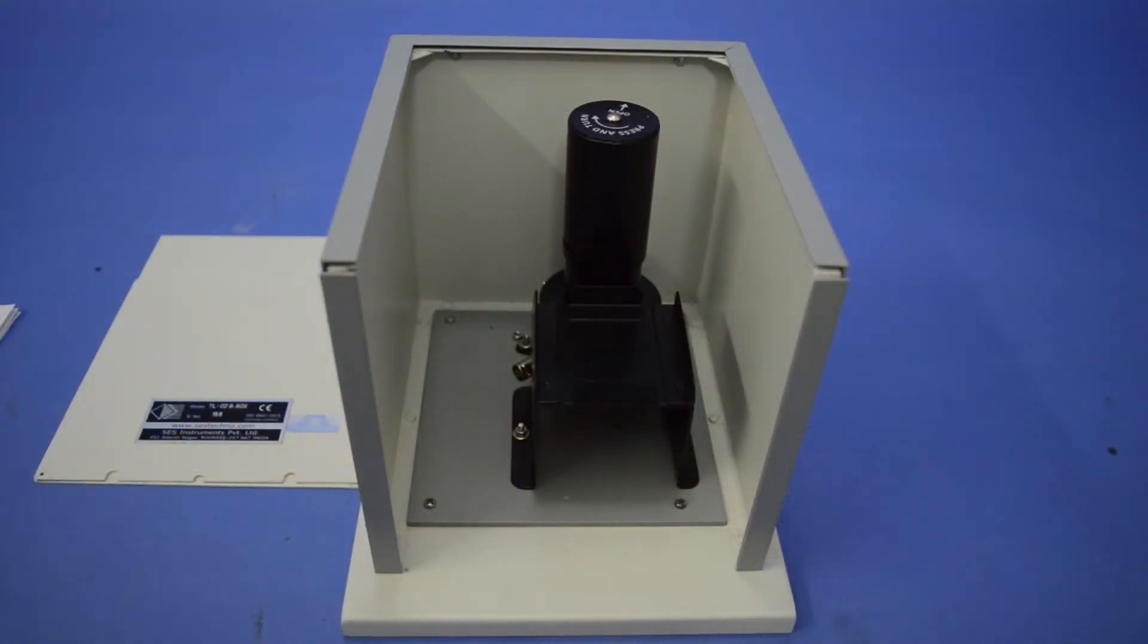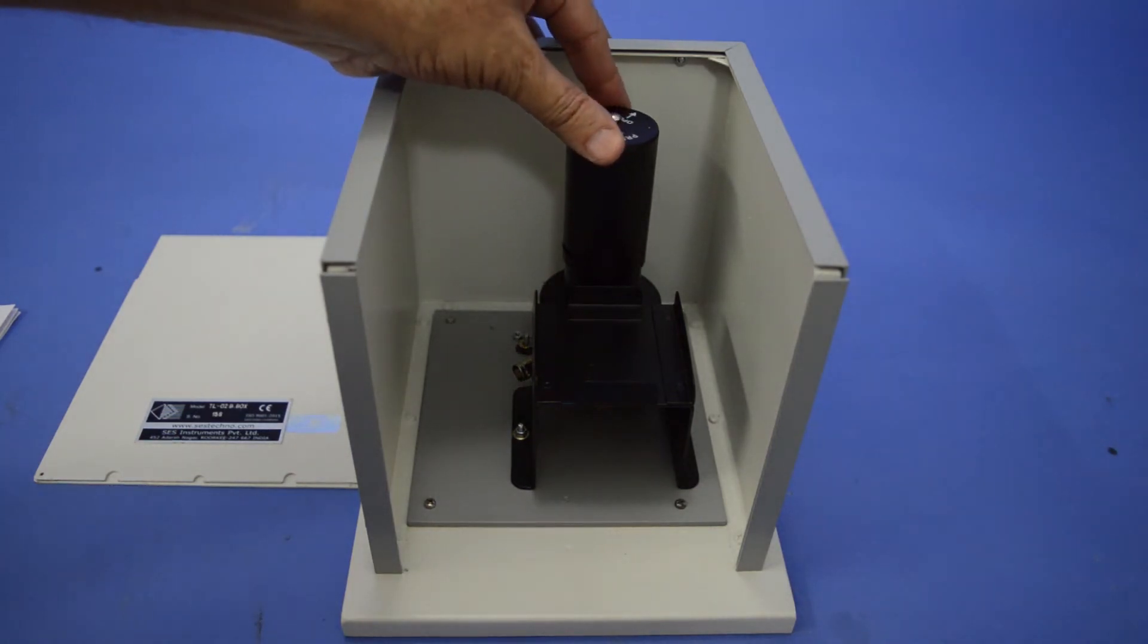To check the working of PMT cover lid, put slightly downward pressure and rotate clockwise and anti-clockwise to open and close the window position.